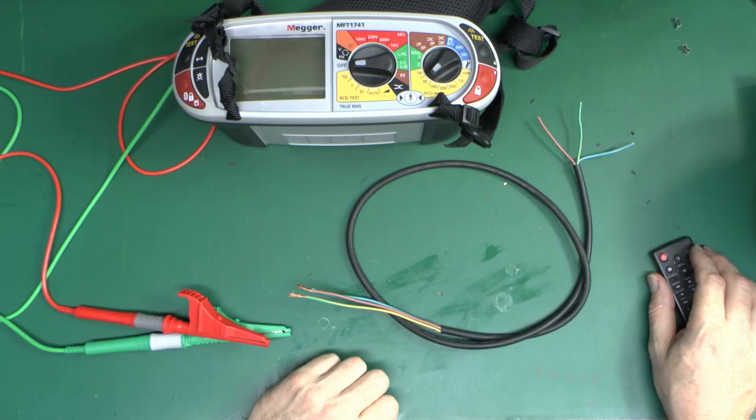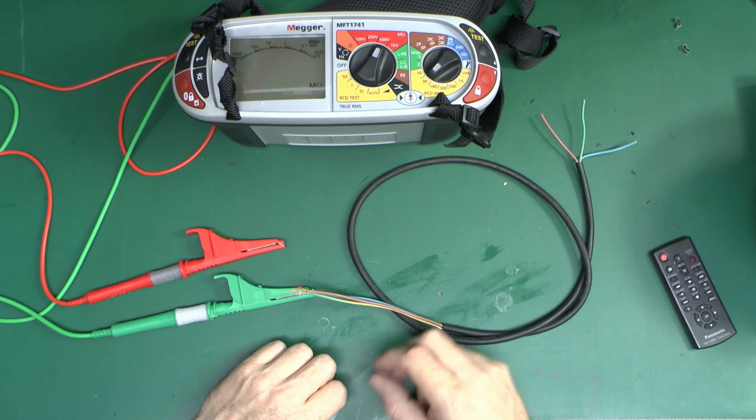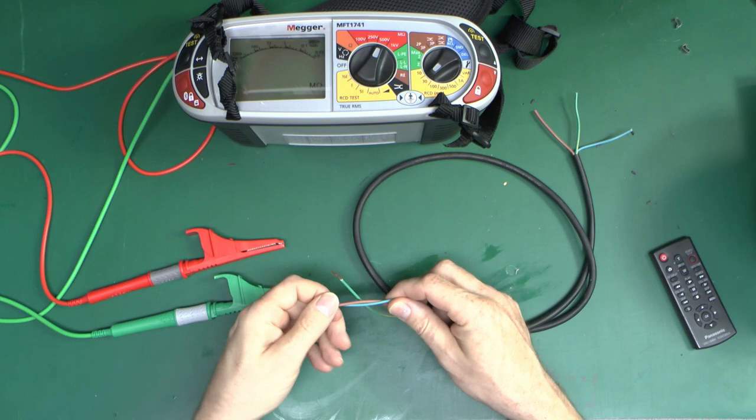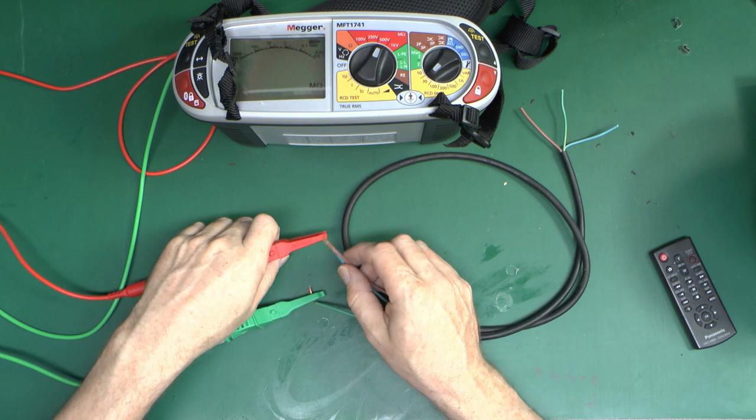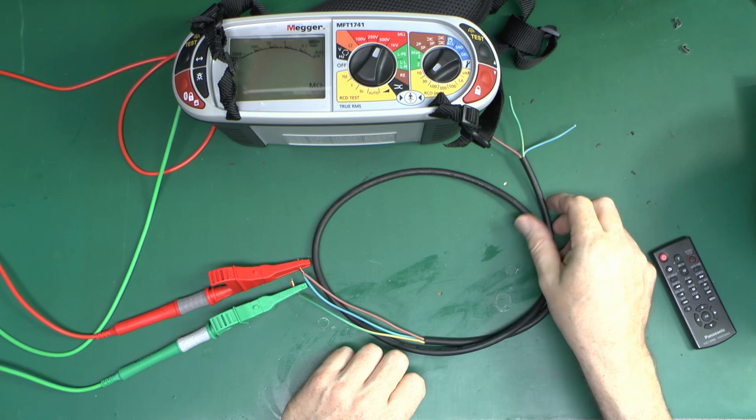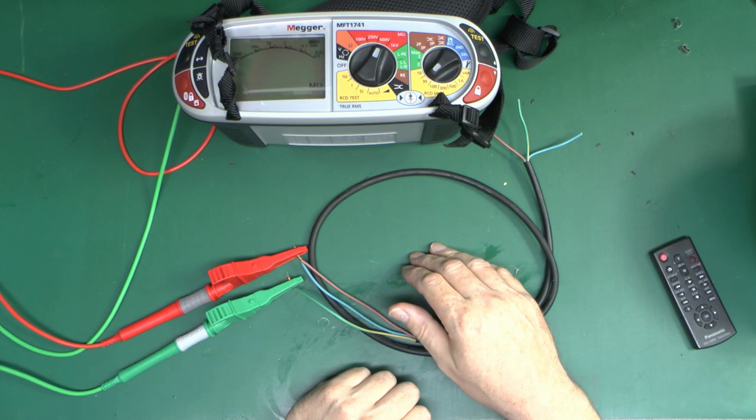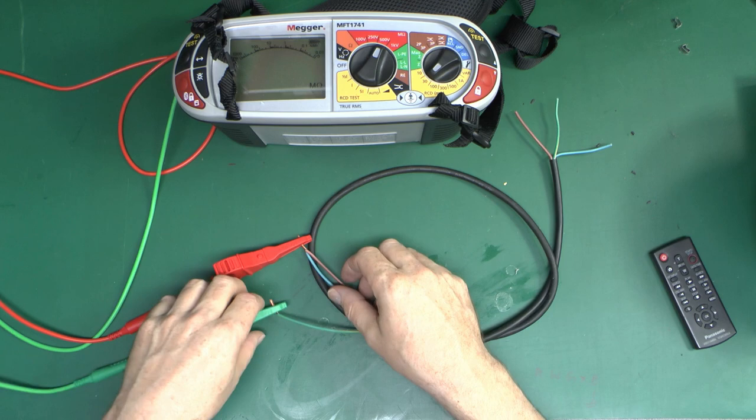Now let's do a little test here with the Megger. And we're going to use insulation resistance, so turn it around to the 500V position. That's generally what you use on a 230V circuit. Now we've got the ends here from the testing previously. So we've got the line and neutral basically twisted together there. And then the CPC, or the Earth there, separate. And that's pretty much how you would test it with a load attached to the end. So we'll just connect up to these. Now when this was outside it had been raining and it was fairly wet. And of course if you get the moisture on the wires here and at the end then of course that can cause fairly undesirable readings. But this has been drying out basically inside for a couple of weeks since then, and there's no sign of any moisture here whatsoever. So you should expect this to test pretty much perfectly. But anyway, let's see what we get.